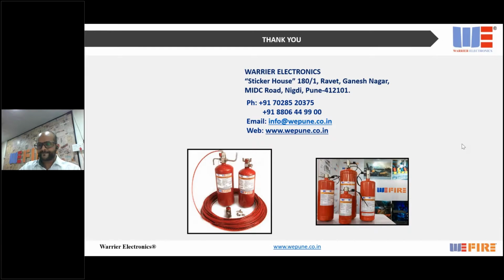And how long can we install these cylinders to the area where they're to be fitted? Like 2 meters for the detection tube? Absolutely, sir, we can do that. The detection tube has to be a maximum of 15 to 20 meters, maximum 15 meters in the nozzle discharge system, not beyond that. But the cylinders are so small that they can accommodate anywhere.